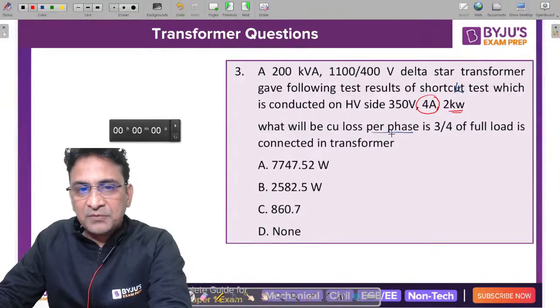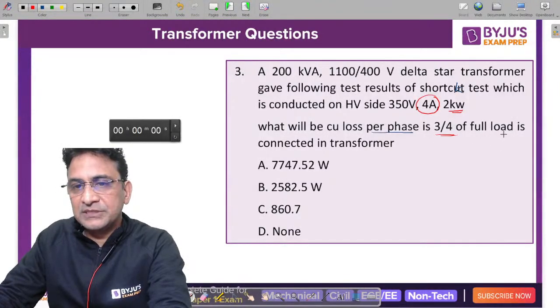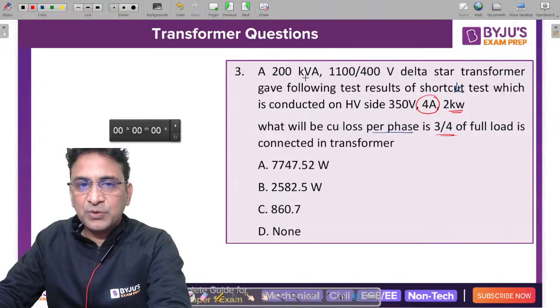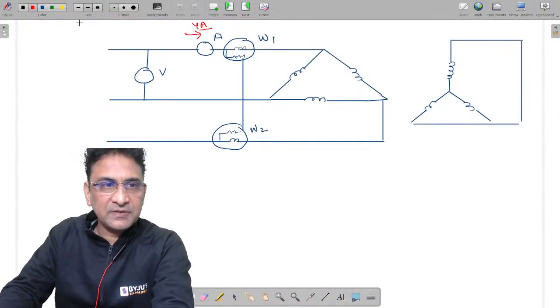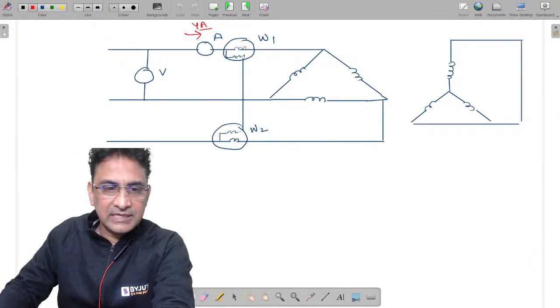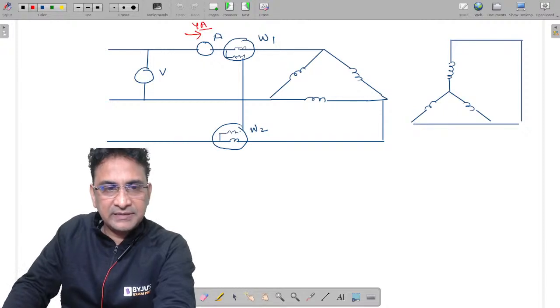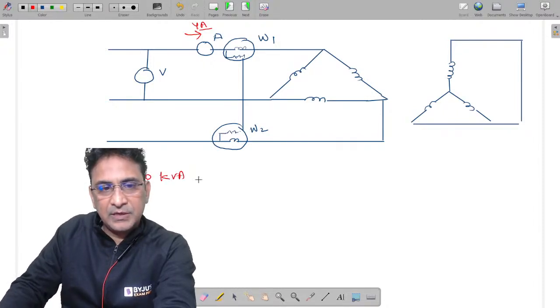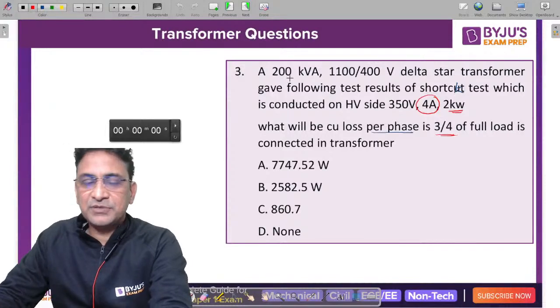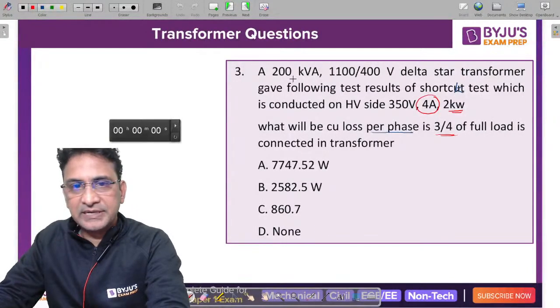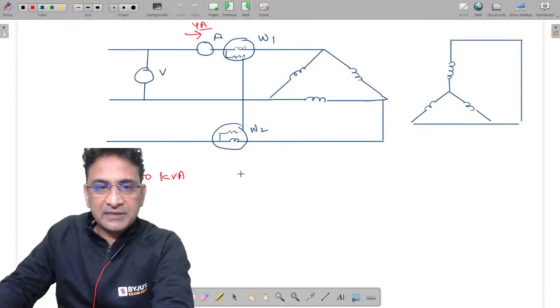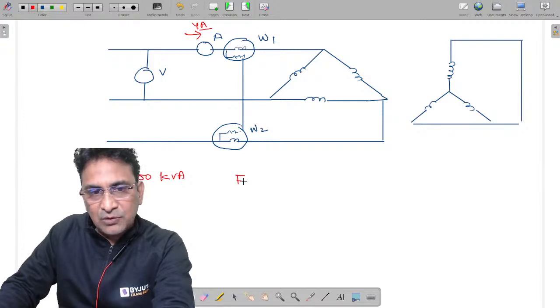See, we have to find out the copper loss when 3/4 of the full load is connected to the transformer. So first I am going to find out the value of full load. 200 kVA is the rating of the transformer. That means it is the input side kVA as well as the output side kVA. So what will be the full load line current?